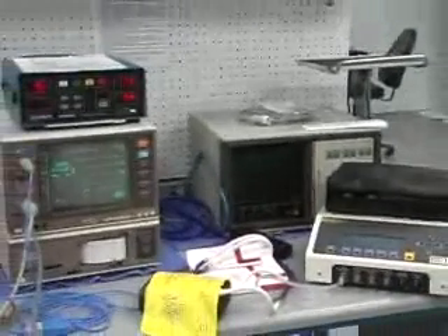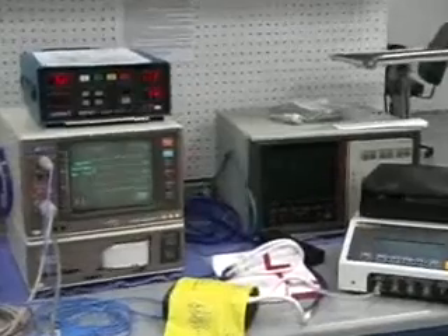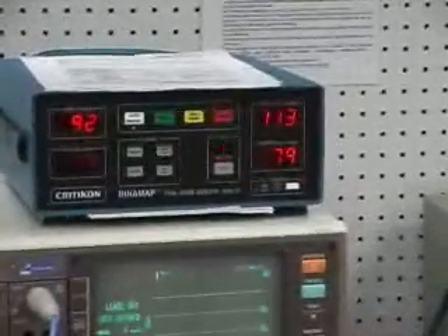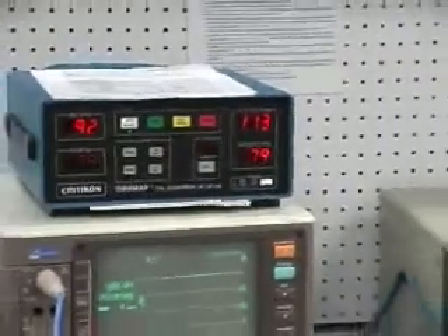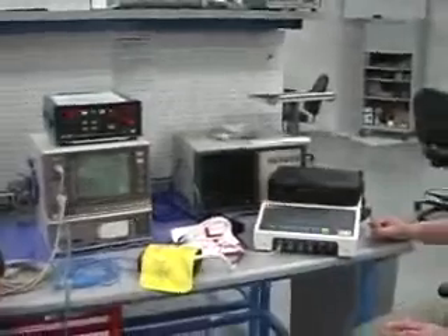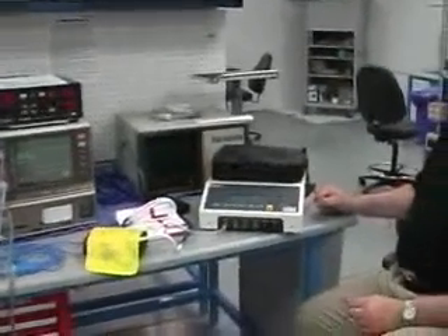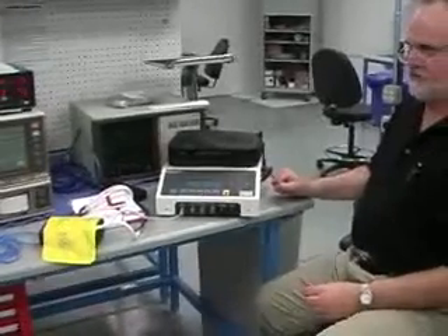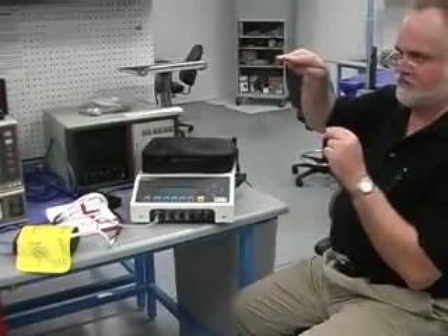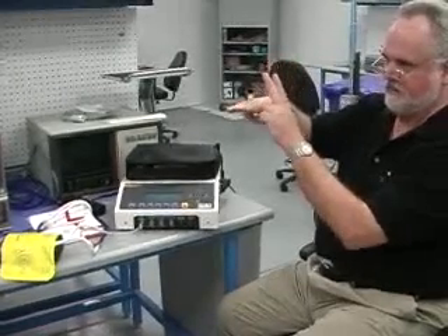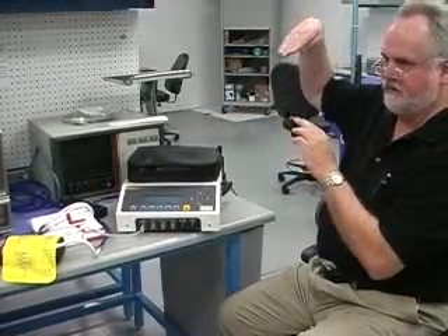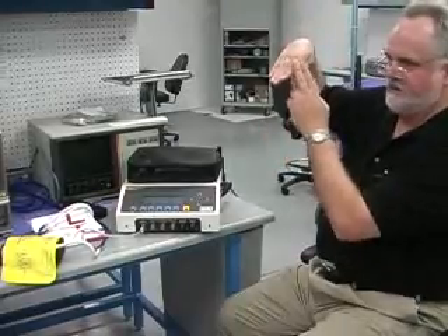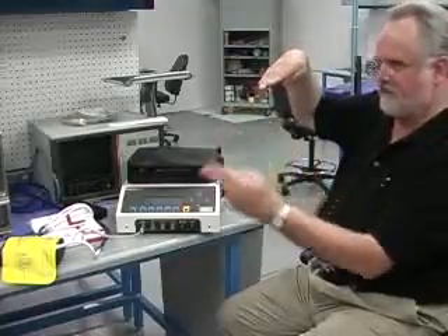Now, if you test other types of devices, it still works. Colin Medical, they're right here in Texas, now owned by Omron. They just bought them a little while ago. Some of the Colin Medical series equipment, the 8800 series and the newer Pressmate series of units, use a linear deflate. So instead of a stepped deflate where it measures 2 pulses, then deflates, it does a linear deflate with a needle valve, and it simply outputs the pulses as it goes down.